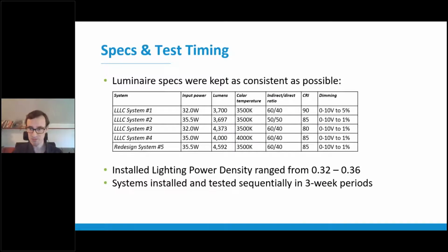Luminaire specs were kept as consistent as possible across input power, lumen output, color temperature, the indirect direct ratio, the CRI, and controls dimming. The installed LPD ranged from 0.32 to 0.36 watts per foot squared, while the baseline sat at roughly 0.6 watts per foot squared. Systems were tested sequentially in 3-week periods between winter of 2018 and spring of 2020.